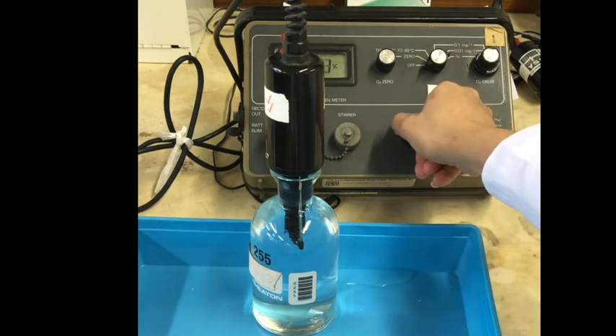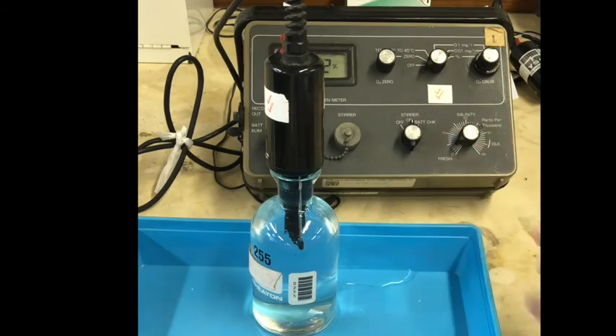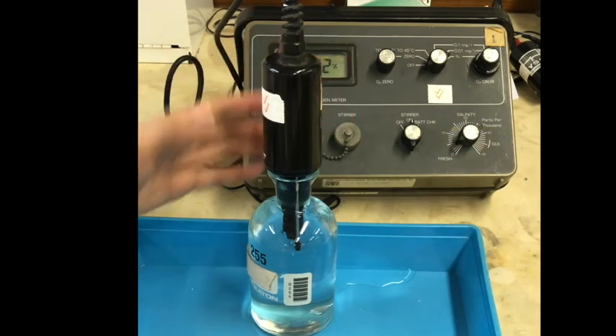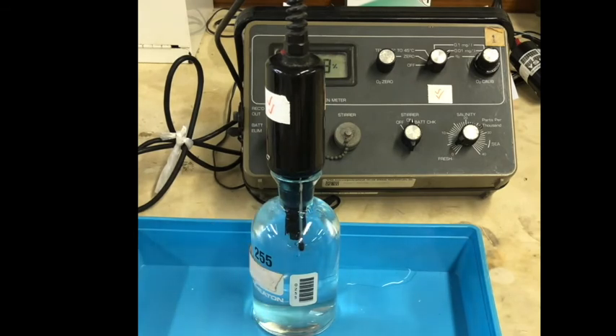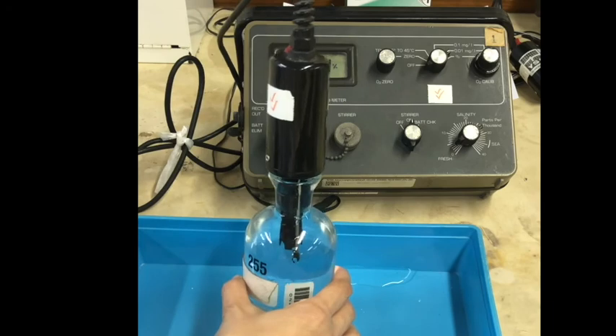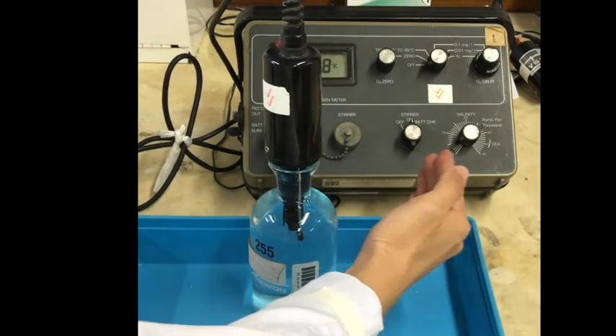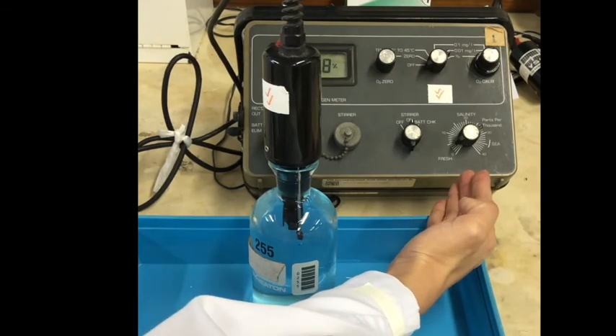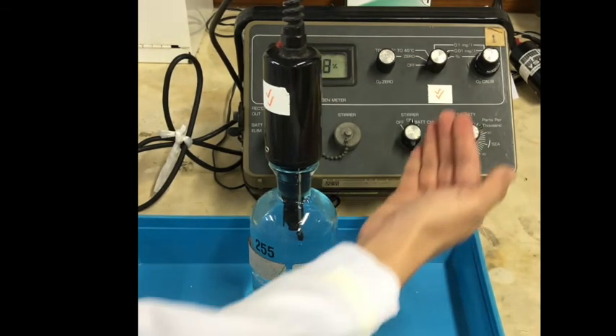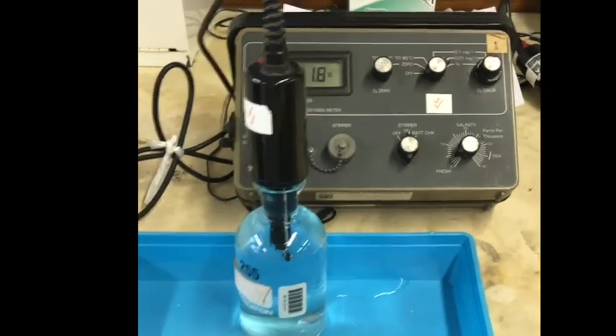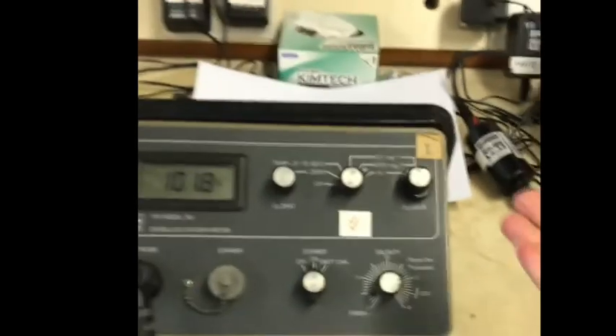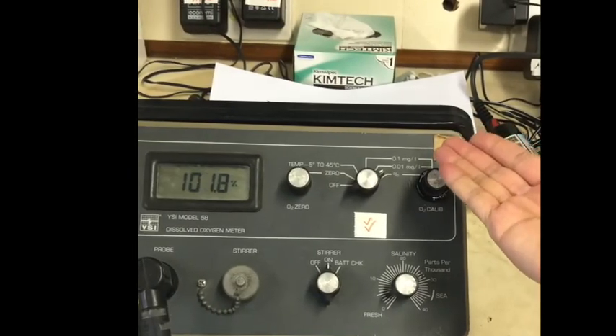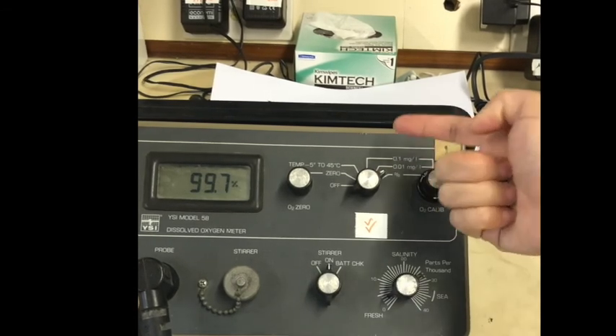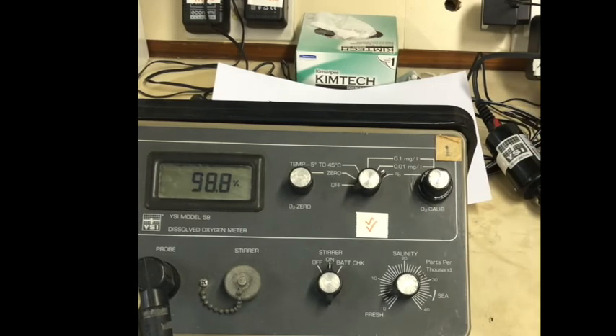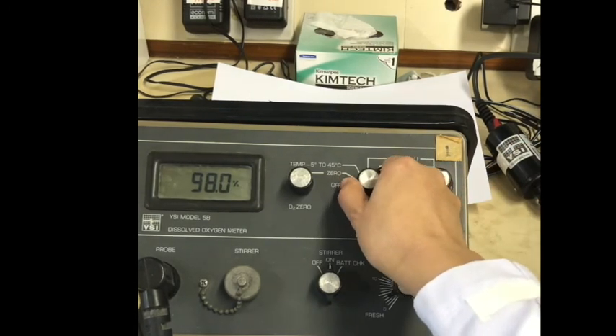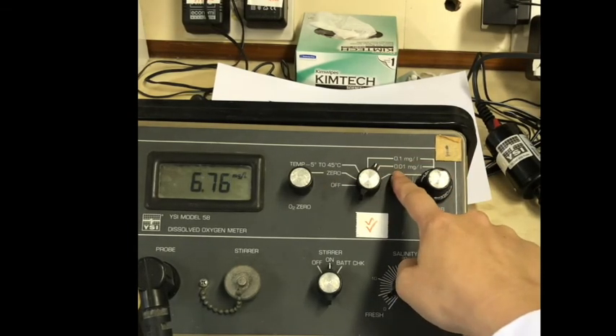Turn on the stirrer. After turning on the stirrer and setting the correct salinity of the sample, now we can take the readings of dissolved oxygen. Set the function switch to the units of dissolved oxygen, mg per liter. The reading of dissolved oxygen can be recorded to 2 decimal places or 1 decimal place. It depends on the amount of dissolved oxygen.